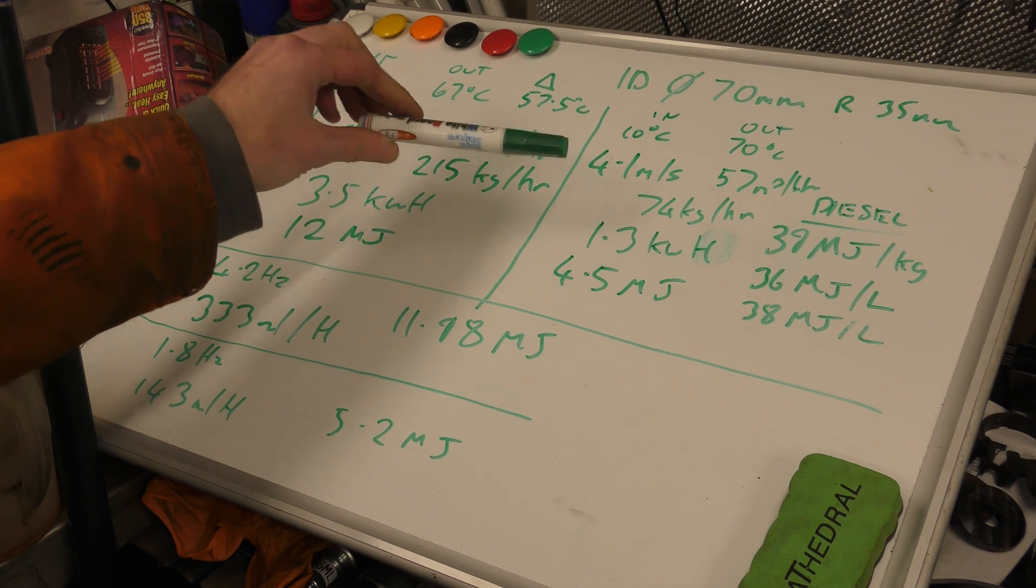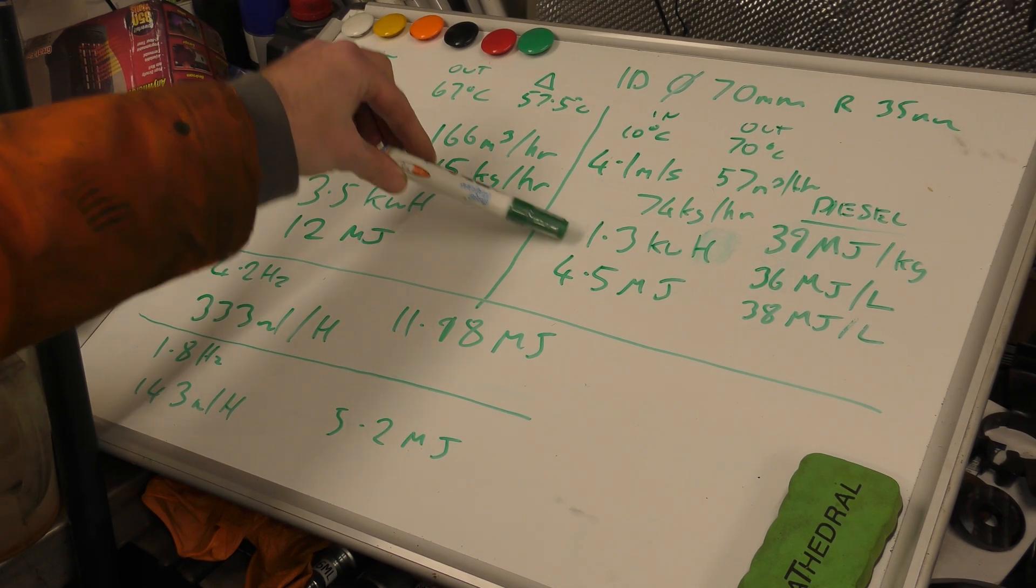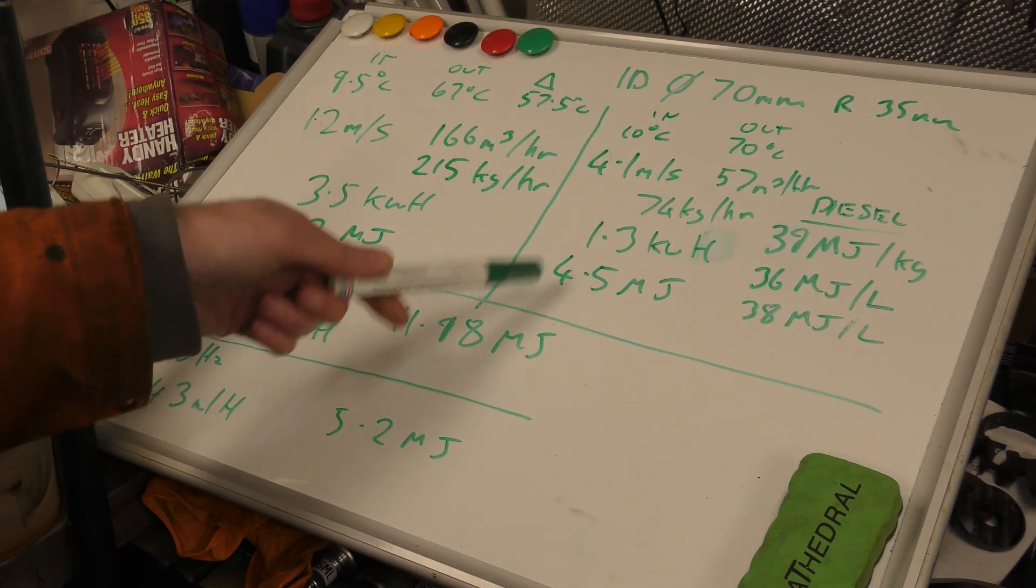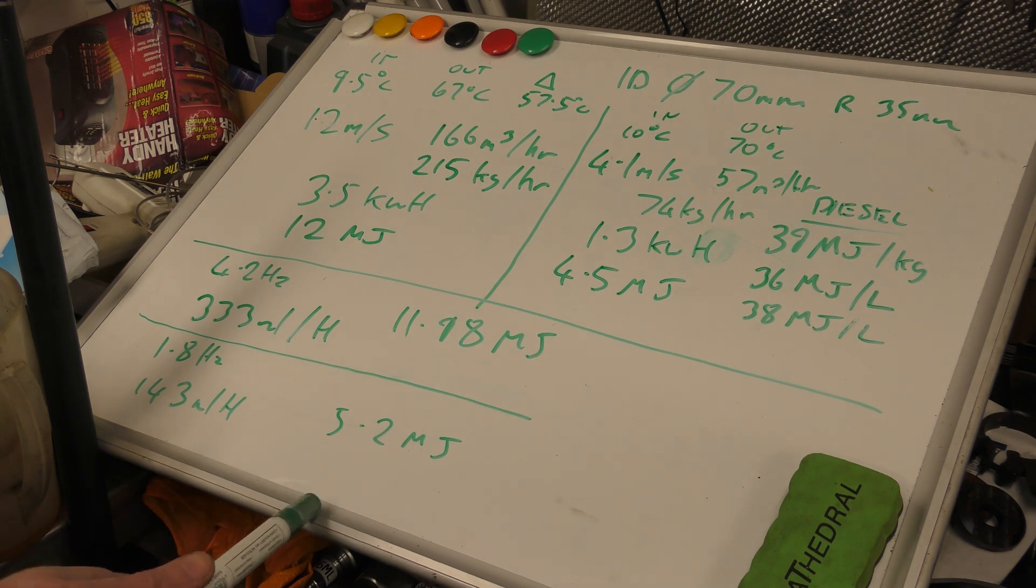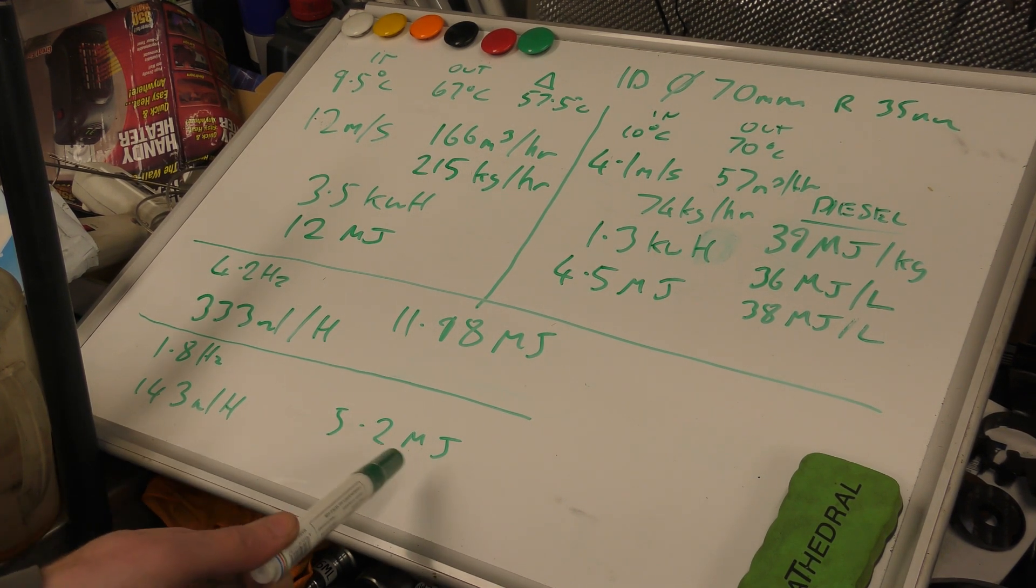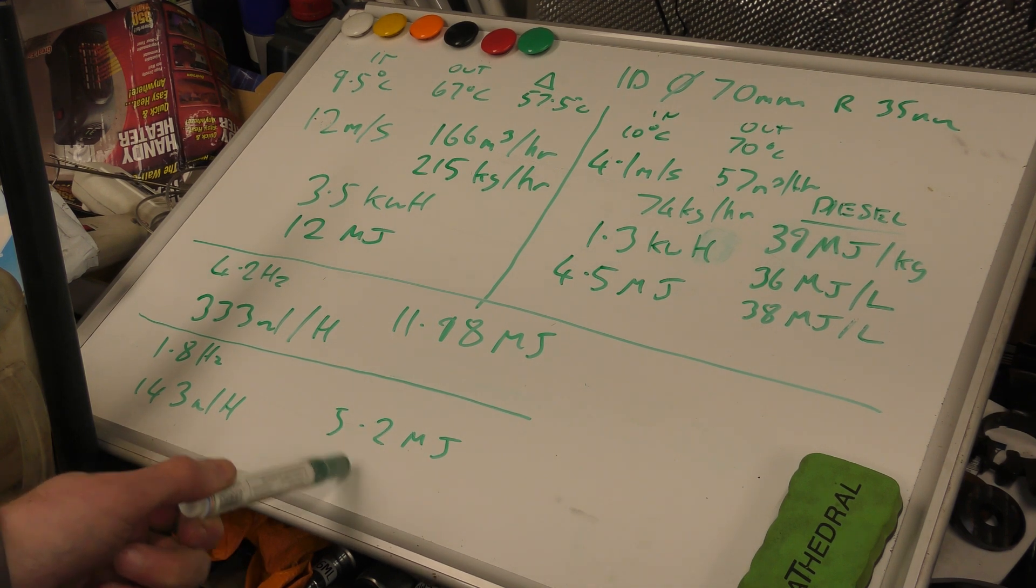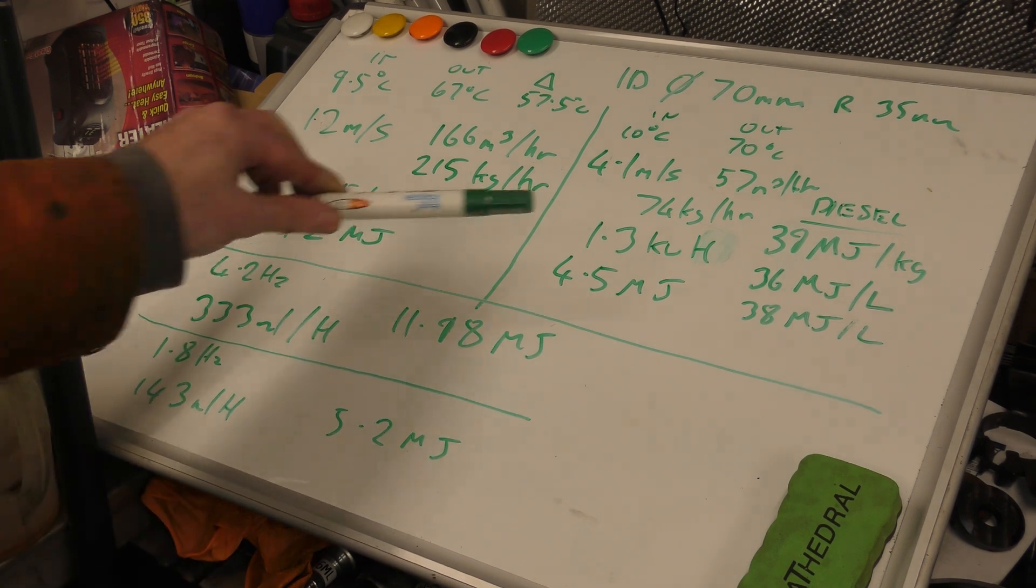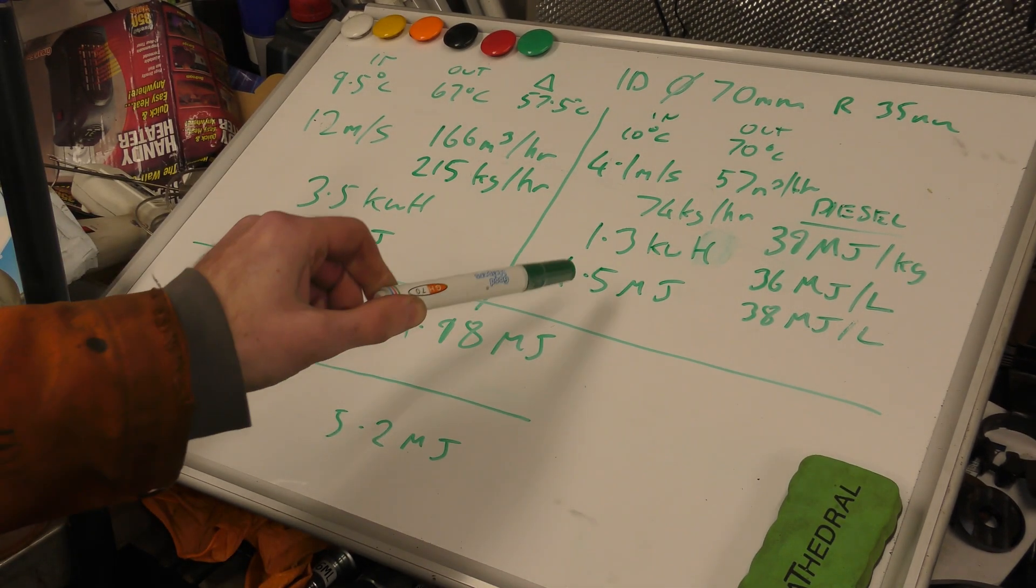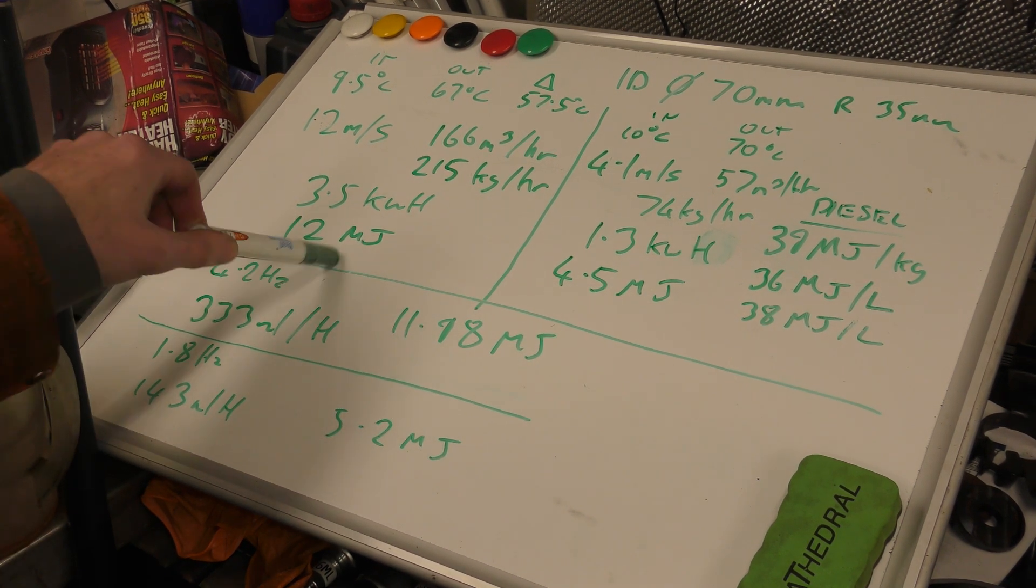This worked out at 1.3 kilowatt hours of heat heated by the heater and 4.5 megajoules. I worked the fueling out at 1.8 hertz, which is 143 millilitres per hour, using 5.2 megajoules of diesel energy. So there's a disparity there, which is good because that's what we'd expect. We don't expect it to output a perfect number this time. That one was too close with too many rounding errors.